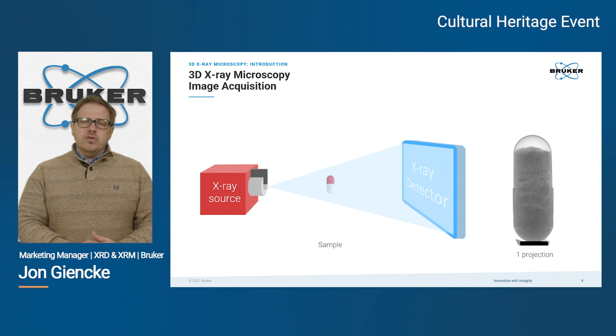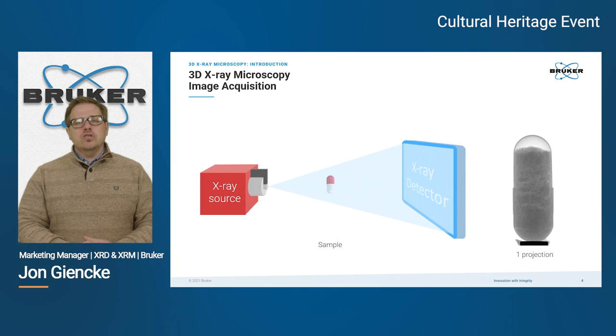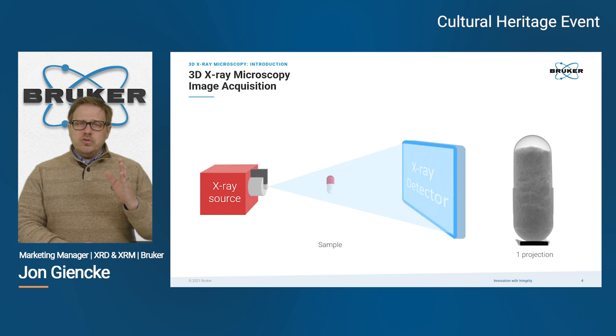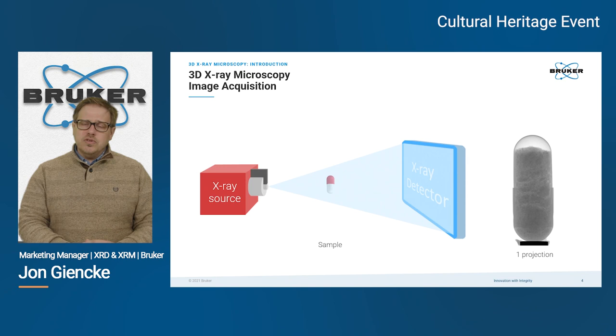One benefit of using x-rays is that they start from a very small origin in the x-ray source which then expands — this is called the cone beam projection geometry, and it affords some magnification. By placing the object closer to the source, we achieve higher magnification and higher resolution. Placing the specimen closer to the detector yields a larger field of view, allowing us to see larger objects in their entirety.